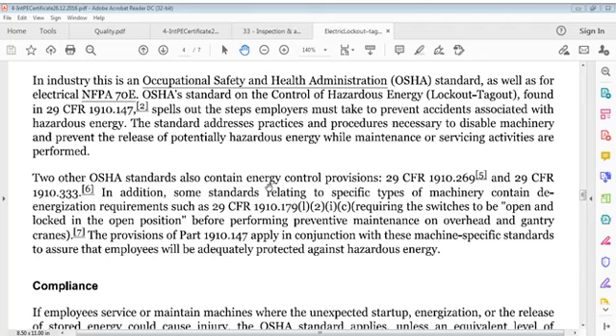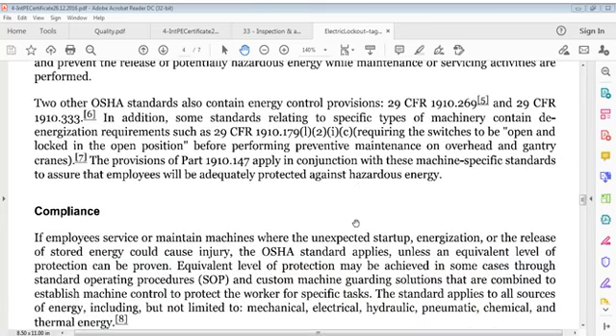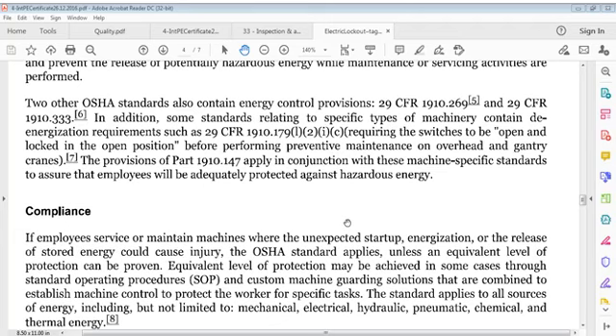Two other OSHA standards also contain energy control provisions: 29 CFR 1910.269 and 29 CFR 1910.333. In addition, some standards relating to specific types of machinery contain de-energization requirements, such as 29 CFR 1910.179(l)(2)(i)(c), requiring switches to be open and locked in open position before performing preventive maintenance on overhead and gantry cranes. Provisions of Part 1910.147 apply in conjunction with these machine-specific standards to ensure that employees will be adequately protected against hazardous energy.